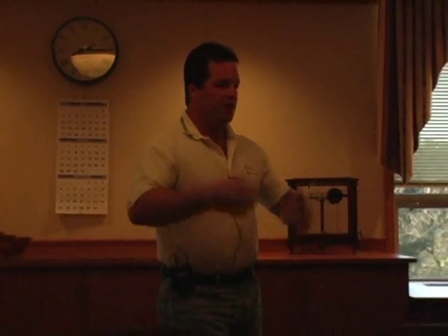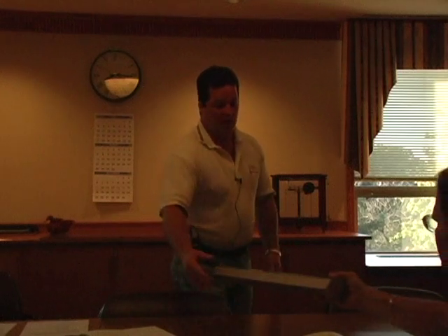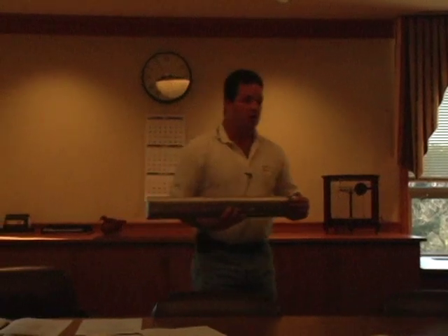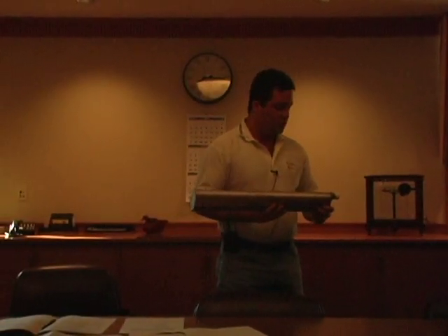The reason why these diffusers are used in a lot of the applications of grit removal and suspended solids and stuff is it gives off a lot of mixing and hydraulics throughout the channels and tanks compared to a fine bubble diffuser system that you have in your others, where you're more trying to get oxygen in the water at a high efficiency rate to deal with your BODs and your biological treatments.